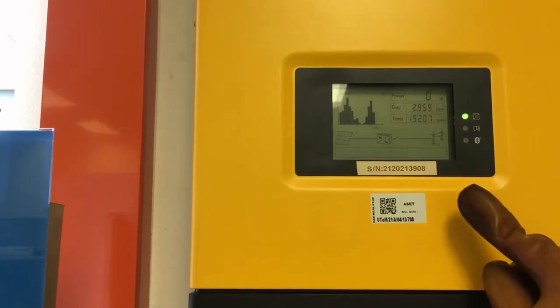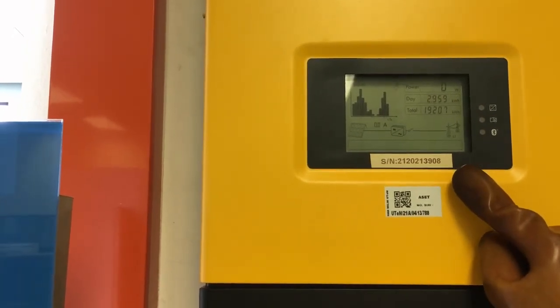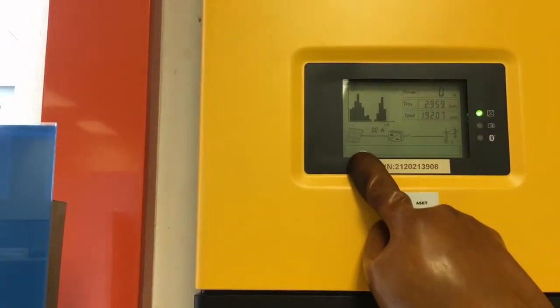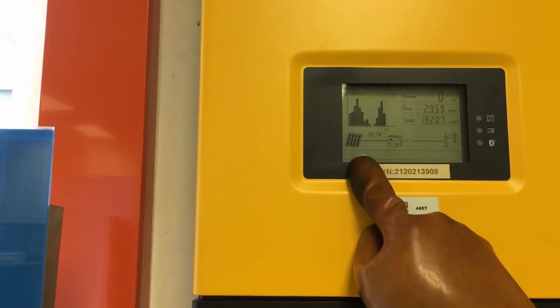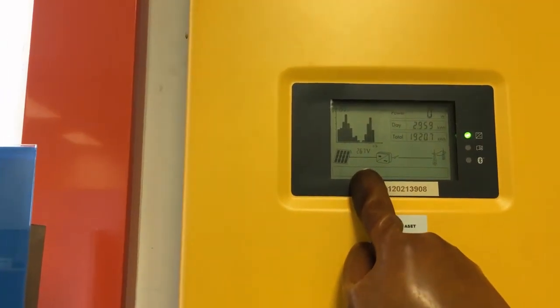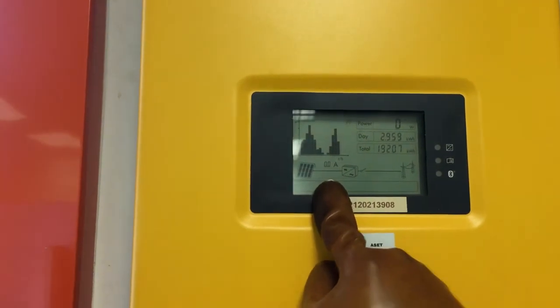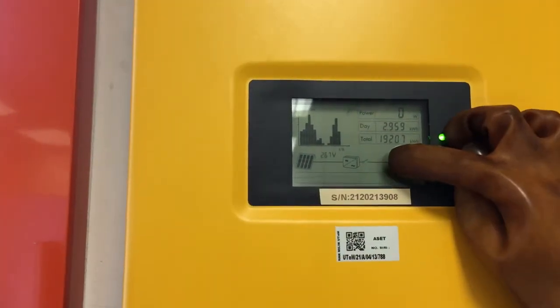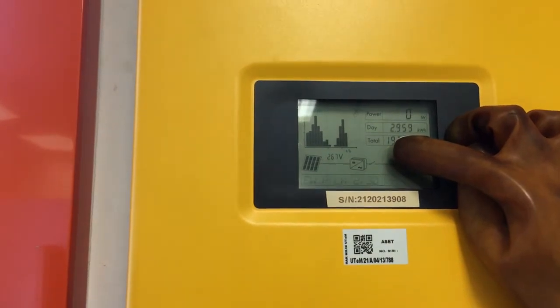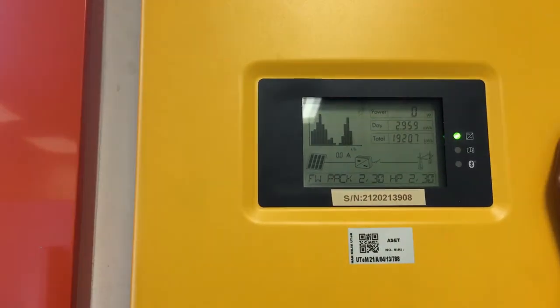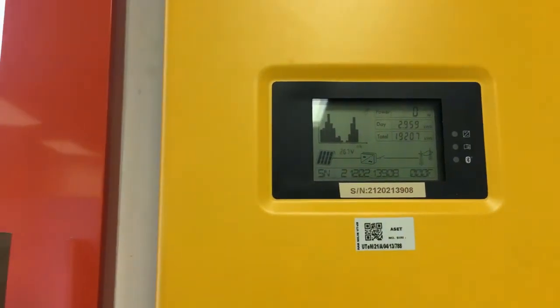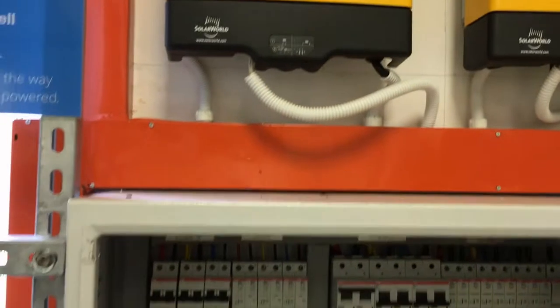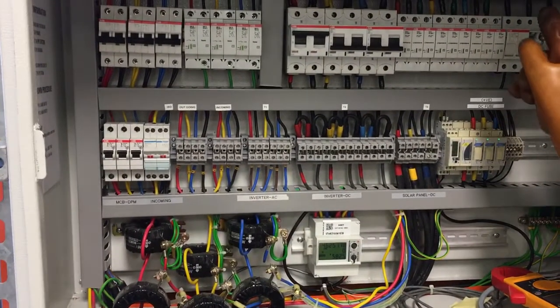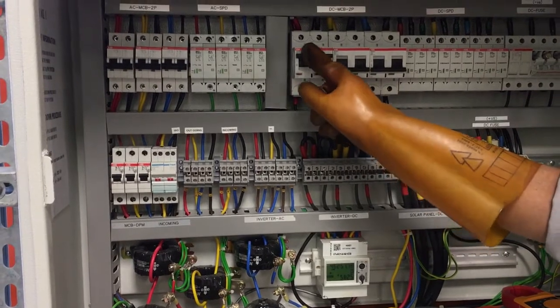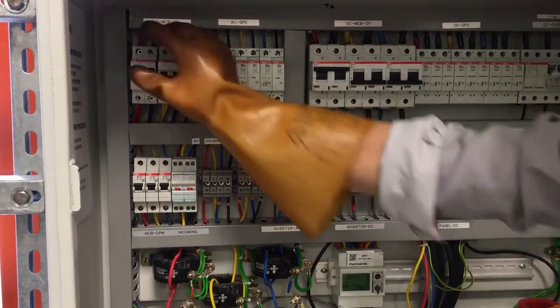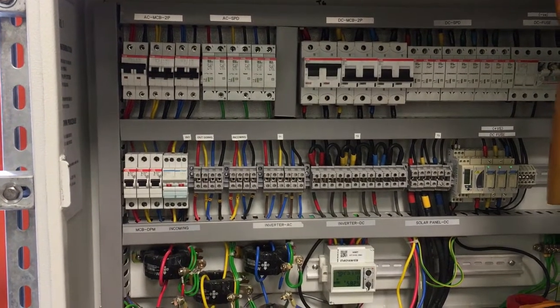Okay, so now you can see the reading from the inverter. So you see that this is the image for the module. The voltage is 267, same as what we measured just now, and the current is 0. Okay, the power is also 0, and the AC side is open circuit because we haven't connected the AC side yet. Okay, so now we are ready. So now we go back to our junction box. So after we turn on the fuse and the DC MCB, now we turn on the AC MCB. And we wait for a while.